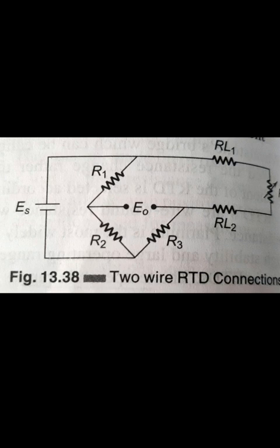Some materials such as carbon and germanium have negative temperature coefficients of resistance. A high value of alpha is desired in the temperature sensing element, so that a sufficient change in resistance occurs for a relatively small change in temperature. This change in resistance can be measured with a Wheatstone bridge, which can be calibrated to indicate the temperature that causes the resistance change rather than the resistance itself.